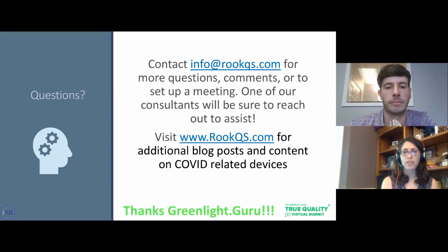Question around what the turnaround time is. Any idea or guidance that you're seeing around that right now? Yeah, we're seeing a few weeks to a month and a half, depending on the product. So I think starting early with communication is key. Reach out as soon as you are close and really clarify what you're trying to do. If it is one of the products that doesn't have specific guidance, then it might take a little longer. But use the tools that are provided with the guidances, the templates, the example IFUs and things like that, to get your submission as close as you can.